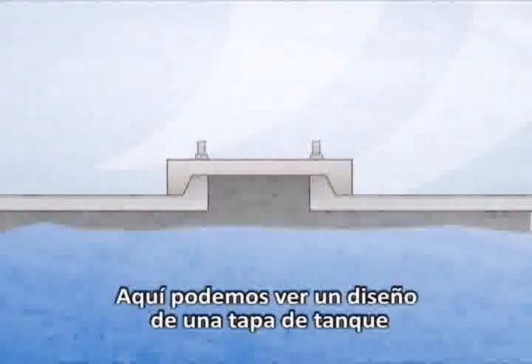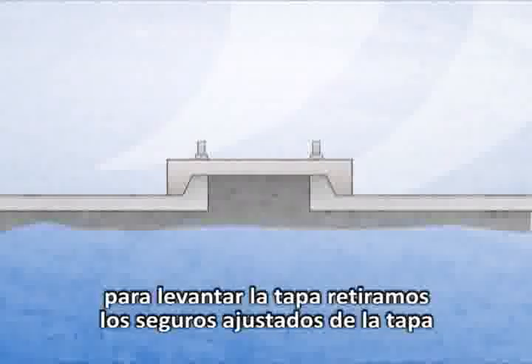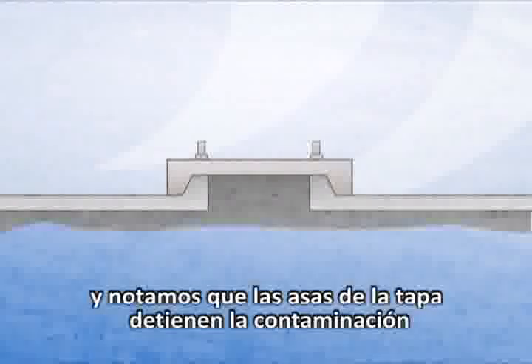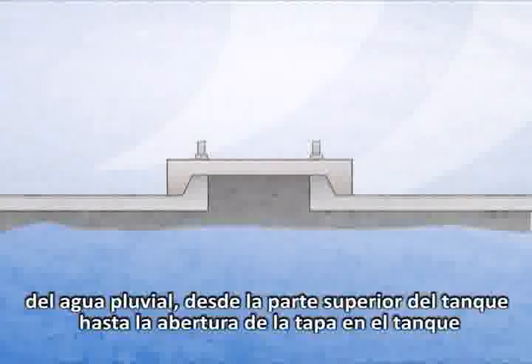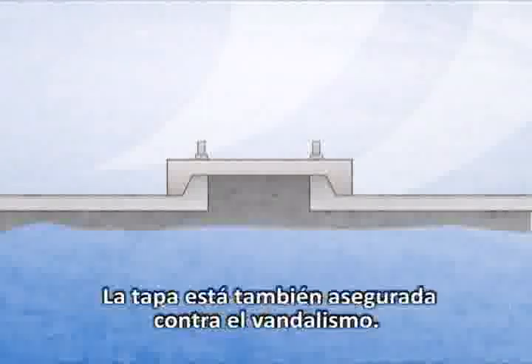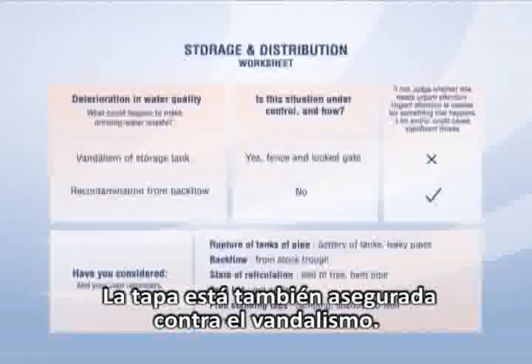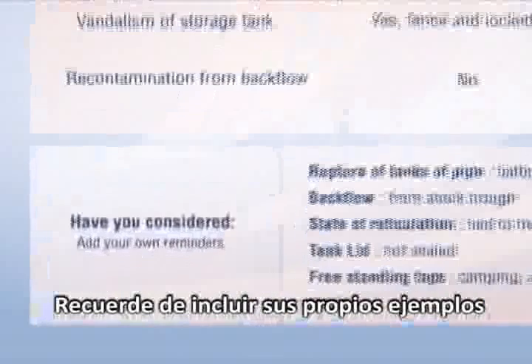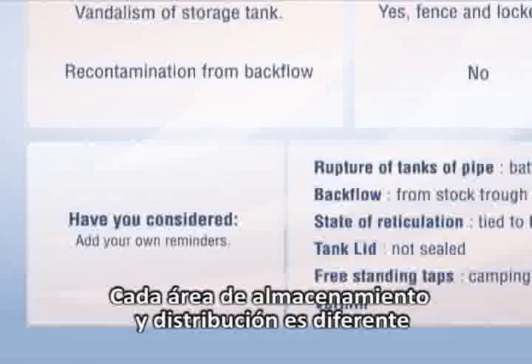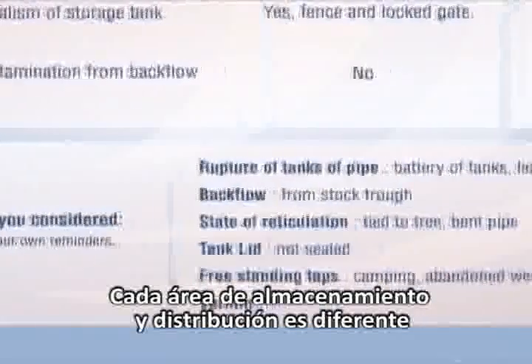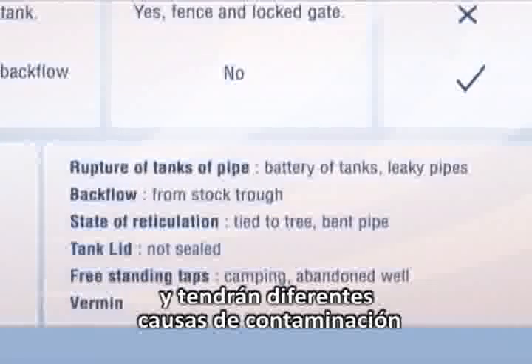Here we can see a securely designed tank lid. The raised lip that the lid fits and an overhanging lid stops rainwater from washing contamination across the top of the tank and down through the lid opening into the tank. The lid is also padlocked to stop vandals. Remember to add your own examples. Every storage and distribution area is different and will have different causes of contamination.